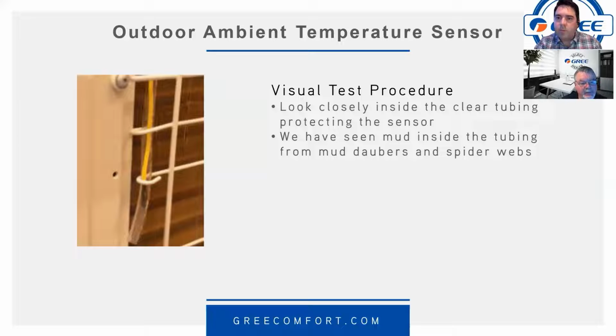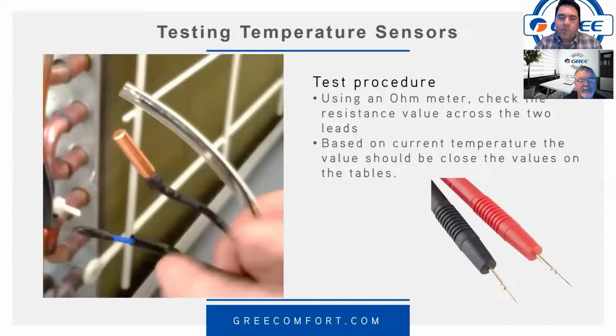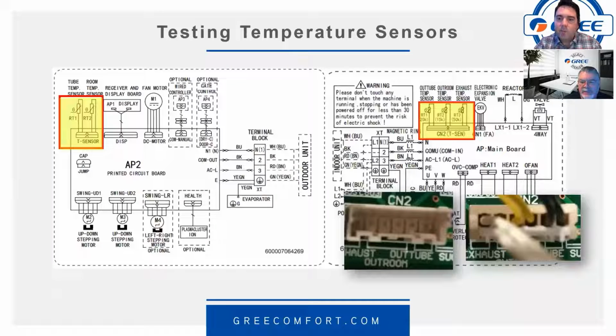And we've got a suggestion on a way to test these in our tips and tricks section. Testing temperature sensors using an ohm meter, check the resistance value across the leads based on the current temperature. The value should be close to the values on the tables. And we just put some updated tables out there for you too, to make it a little bit easier. Got an example of that coming up.